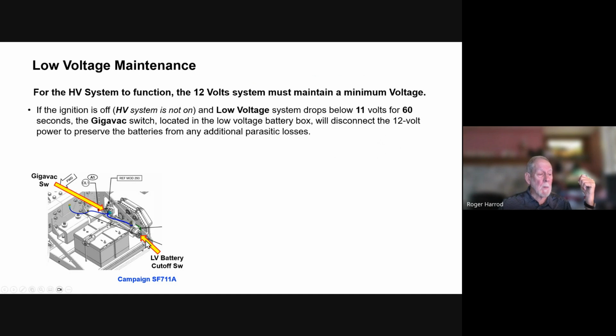So we just went through a campaign. In fact, here's the campaign number. We added what's called a gigavac switch, which is located right here in the battery box. It continuously sources or identifies the voltage from the batteries, and when it drops below 11 volts for 60 seconds, it breaks the connection. So there can't be any more parasitic losses. That should allow us to restart without any problem.